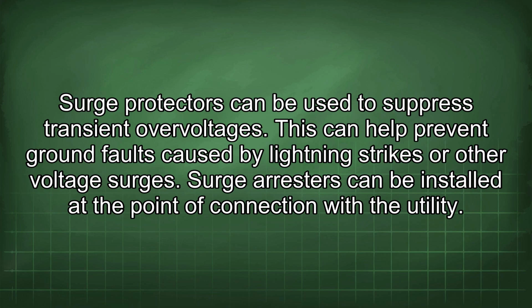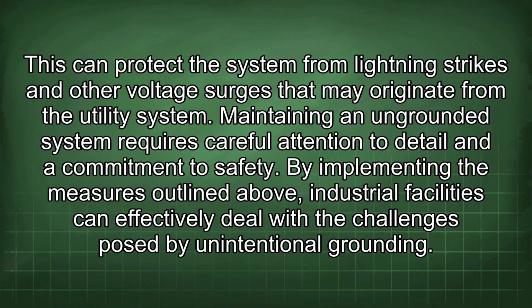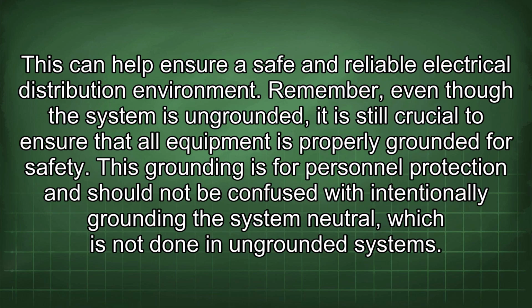Surge arresters can be installed at the point of connection with the utility. This can protect the system from lightning strikes and other voltage surges that may originate from the utility system. Maintaining an ungrounded system requires careful attention to detail and a commitment to safety. By implementing the measures outlined above, industrial facilities can effectively deal with the challenges posed by unintentional grounding. This can help ensure a safe and reliable electrical distribution environment.